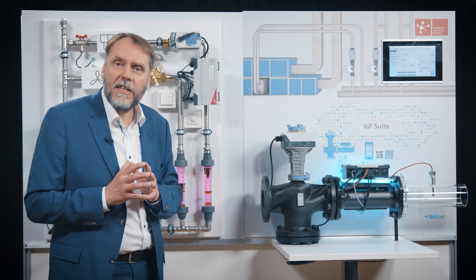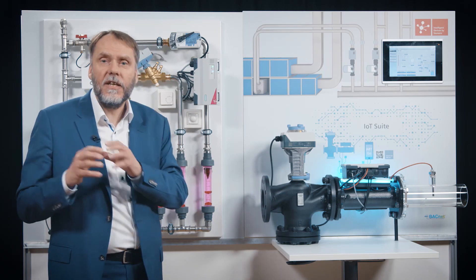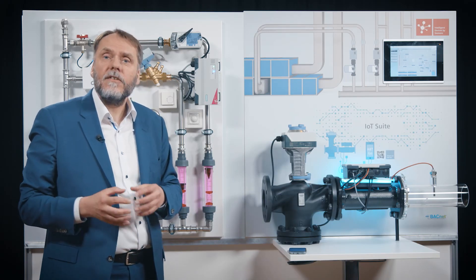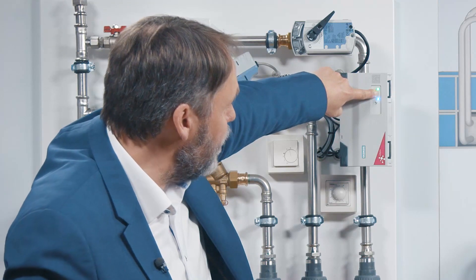On the one hand, to do the pre-setting for the hydraulic balancing. On the other hand, during operation, to get information about the current flow situation, about the temperature situation in the plant, and also about the communication status into the building automation network. As a mechanical contractor, during the commissioning phase, you can connect to the device directly and do all the pre-setting with our ABT Go app. You can balance the system just by a fingertip — you can change the maximum pre-setting on this device and get an immediate reaction when the device is running. Besides that, you can also activate a self-test of the device to get confirmation that the pre-setting you have done is properly working. You can use the manual push buttons on the device for that as well.